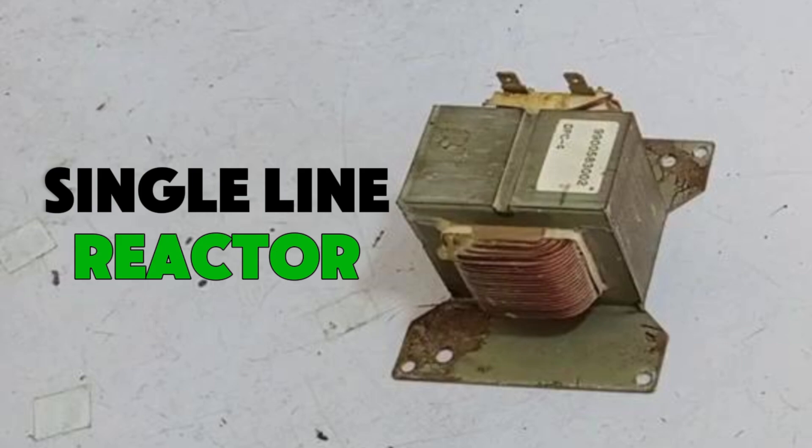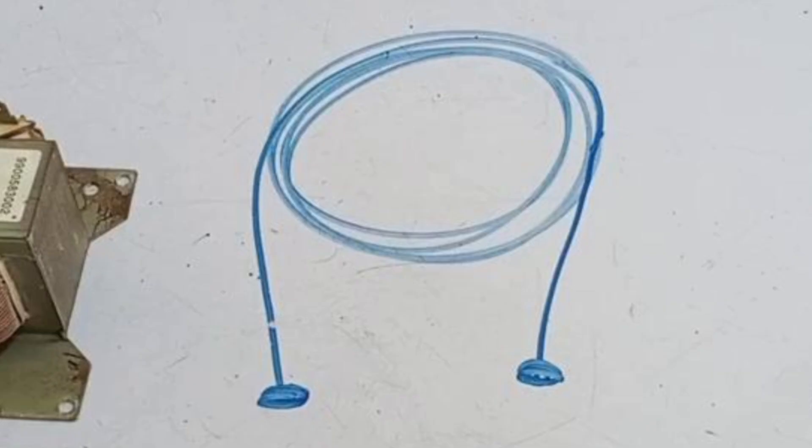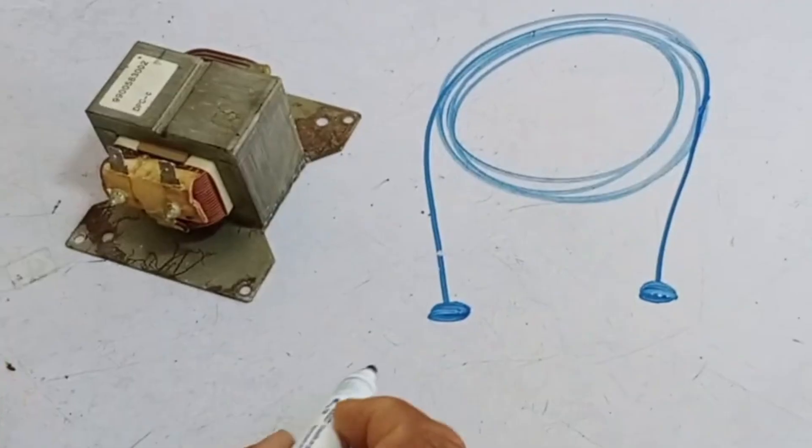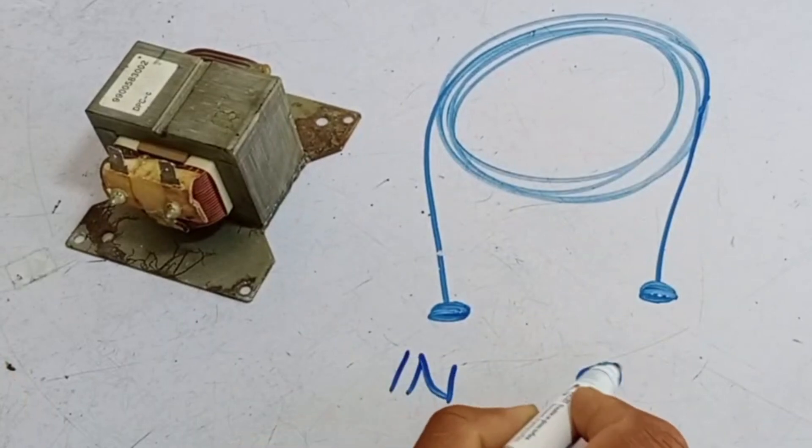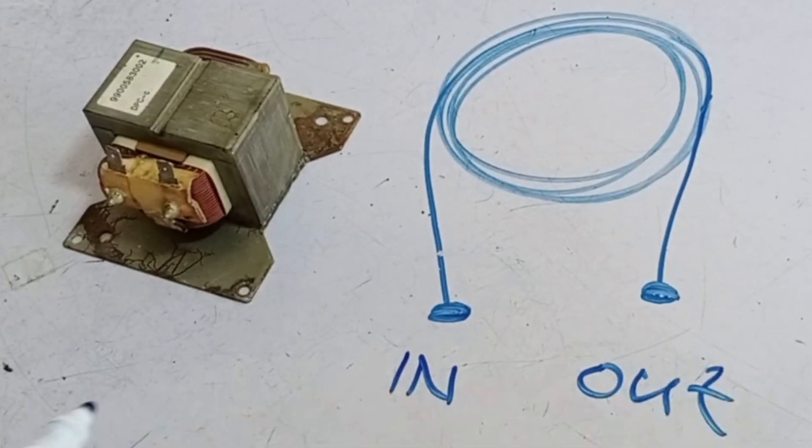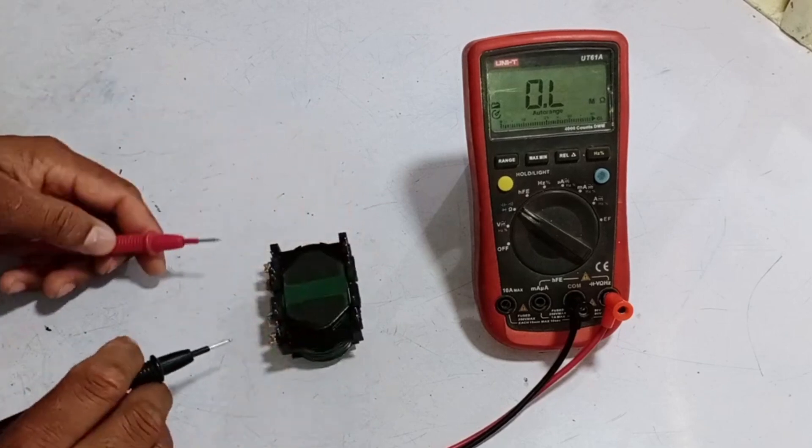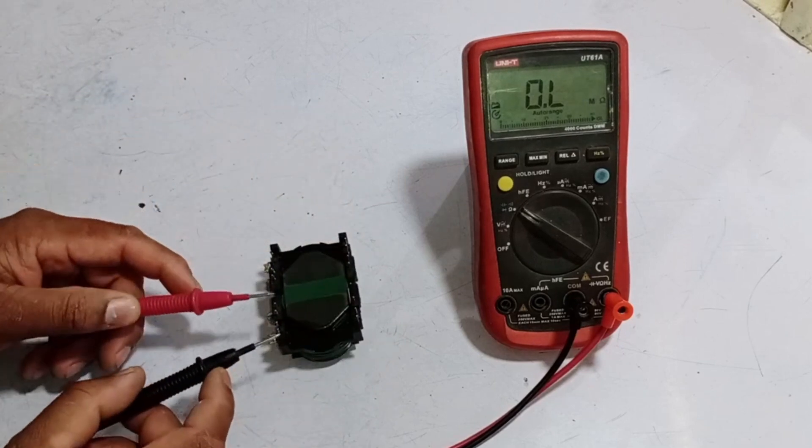Now, if we talk about this single line reactor, it contains a single coil that is wound in a circular manner. One side serves as the input, and the other side acts as the output. This is how it operates. Now, I will explain how to test it. There are eight points to check, and we will test them step by step.